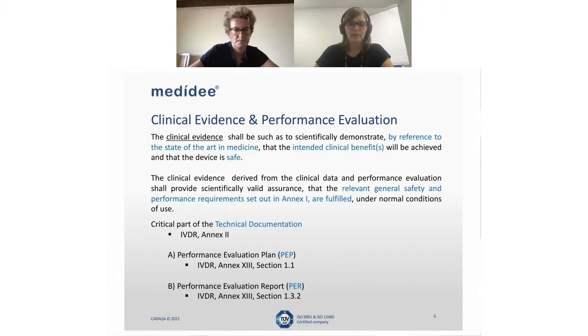So this clinical evidence, as already mentioned before, needs to demonstrate that the device meets the relevant general safety and performance requirements, so GSPR 1, 8, and 9. And it is then illustrated as part of the technical documentation, where under IVDR Annex 2 it is stipulated that the technical documentation needs to contain a performance evaluation plan, and this for all IVD medical devices, no exception at this level. And it also needs to contain a performance evaluation report, or PER.